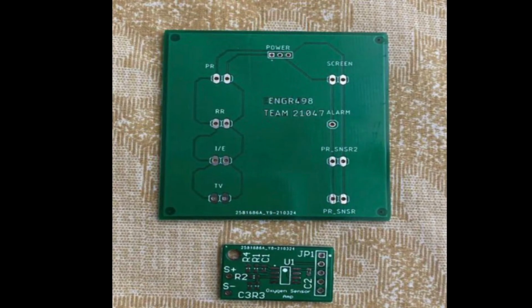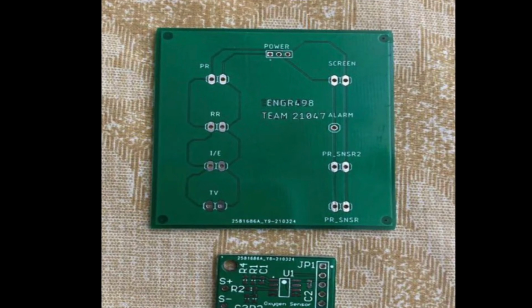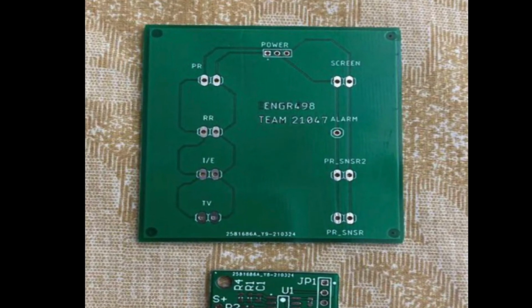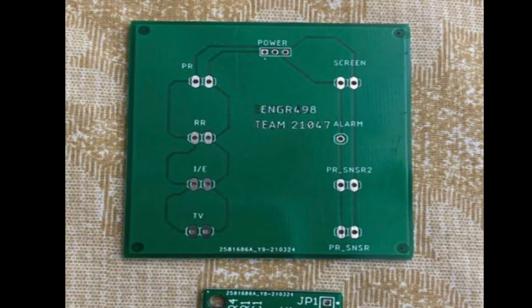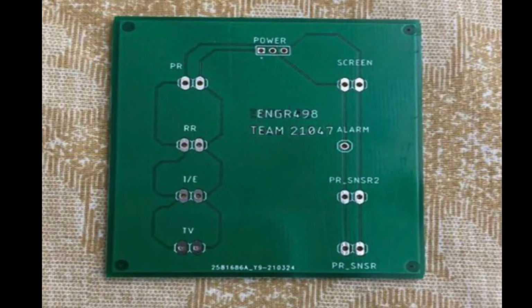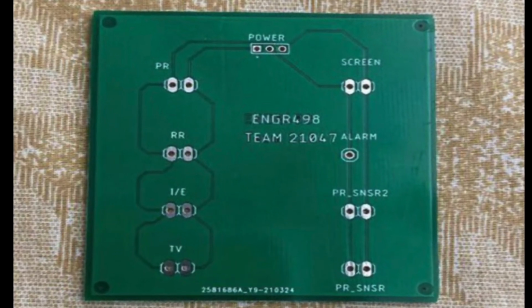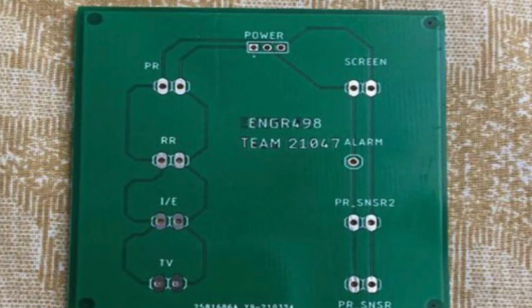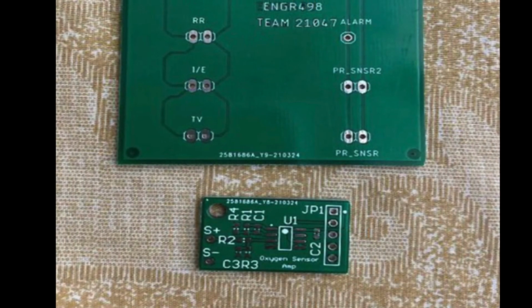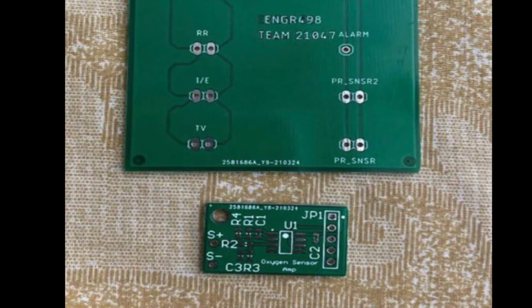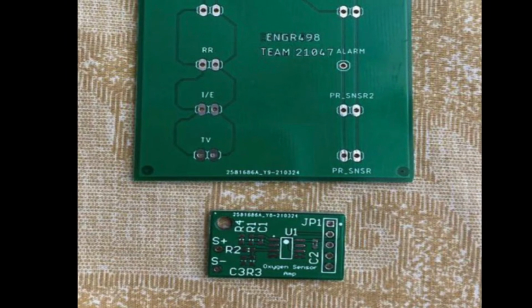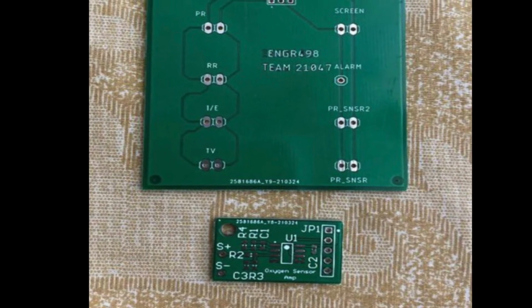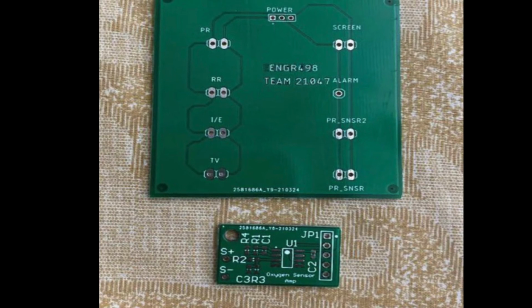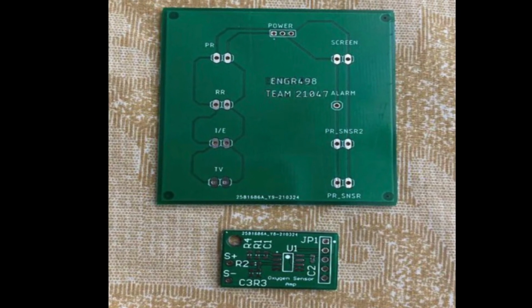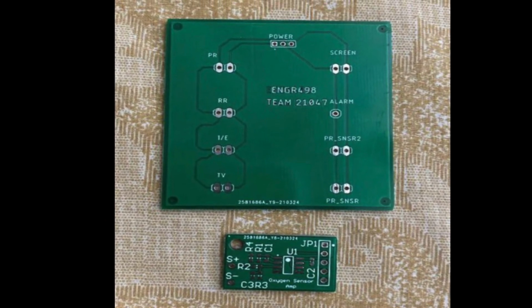Our ventilator uses 2 separate printed circuit boards. The top circuit is used for potentiometers, LCD screen, pressure sensor, and our alarm system. The bottom circuit board is used only by our oxygen sensor. We needed to fabricate a separate PCB because our voltage supplied to our oxygen sensor is substantially lower than the voltage supplied to the rest of the components. Our circuit boards were designed using Eagle software and fabricated by JLC PCB Fabrication.